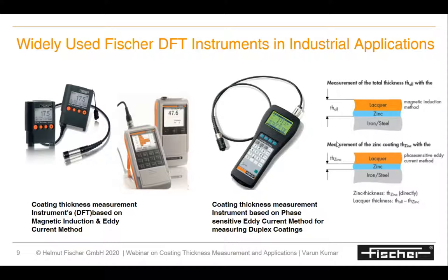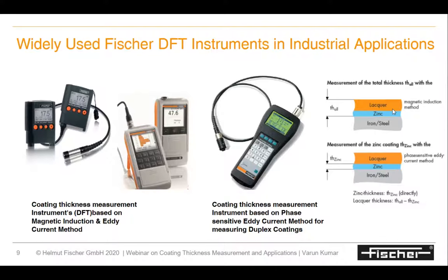Instruments from Fischer include DFTs, the Dualscope MPOR, and phase-sensitive eddy current instruments. There is also the PMP10 Duplex instrument — designed for the automotive segment where galvanized sheets are painted. Some customers need to measure both paint thickness and the zinc plating on the metal sheet. The PMP10 Duplex uses phase-sensitive eddy current to measure the zinc layer and paint layer simultaneously — the biggest advantage of this particular instrument.